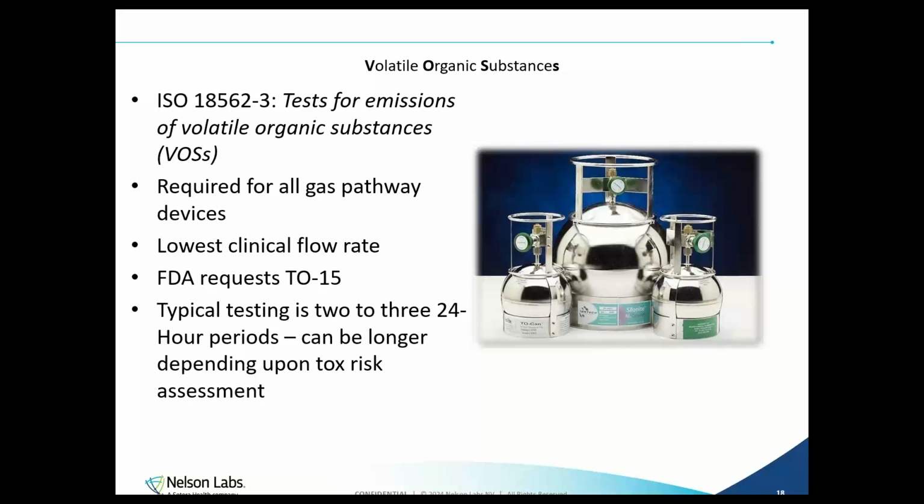The length of time for this VOC sampling should be multiple 24-hour periods. It is typical for sampling to occur in 3 separate 24-hour periods, even for long-term devices. This gives us 3 whole days worth of data. The first 24 to 48 hours, 48 to 72 hours, and then we could look at any sort of release kinetics from the chemicals seen. However, if there are expected to be a lot of volatiles to come off the device, it may be a benefit to increase sampling out to 3 or 4 days.